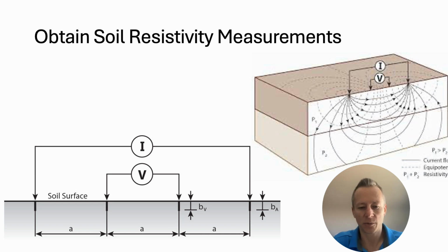Now you can see in the picture what's typically done is the 4-pole Wenner test method. 4 probes are driven. You can see they're equidistant between them based off the A dimension in the lower left picture. Current is injected on the outer probes, and the voltage is measured on the inner probes. And they're divided out, and they give you a resistance value. And there's an equation that will turn that resistance based off the probe spacing into a resistivity for the soil. And it's essentially measuring the soil as its entire collective makeup.